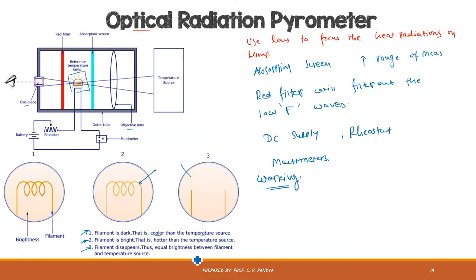Under that condition it will be very difficult to distinguish the color of the filament from the light coming from the source, so the filament will apparently become invisible — this is the third condition where the filament disappears. The brightness of the filament equals the brightness produced by the temperature source. This reading is taken as a reference and the meter is calibrated in terms of temperature, so it will directly indicate the magnitude of temperature.